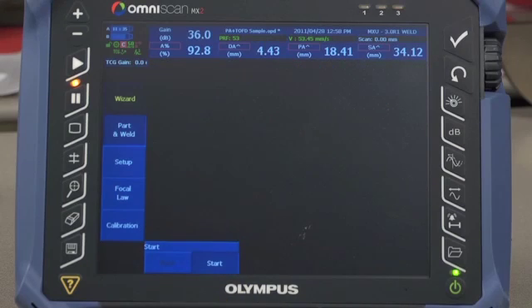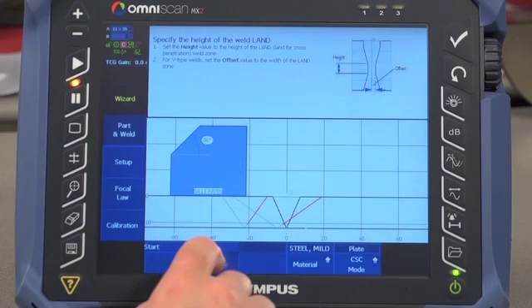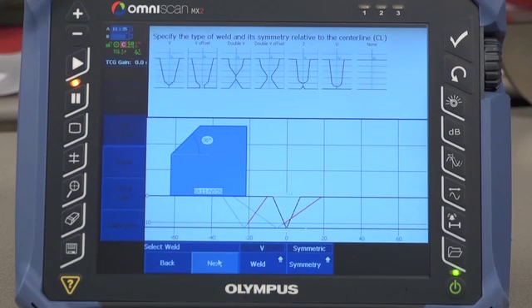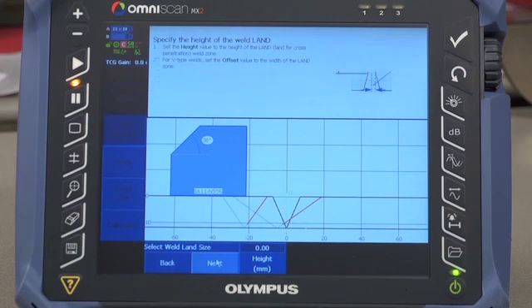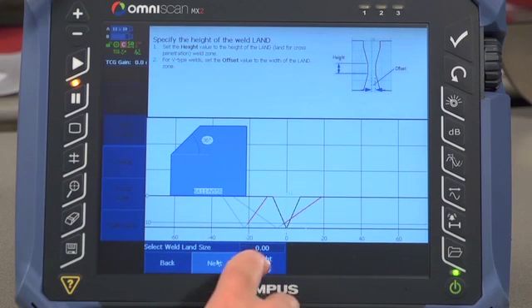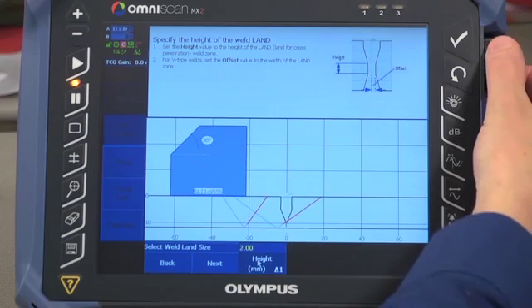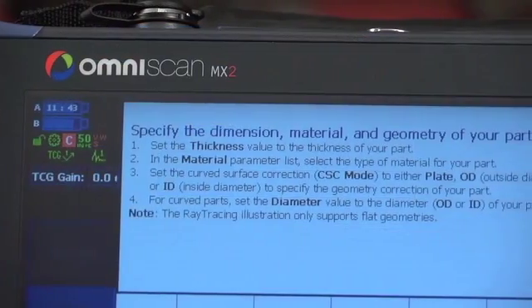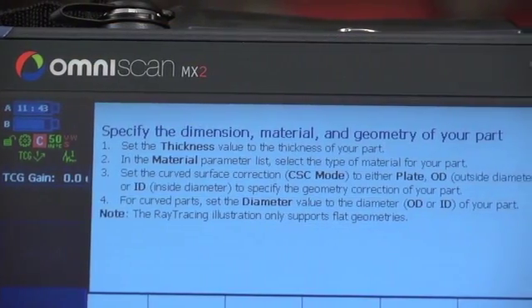Ultrasonic, TOFD, and phased array setups, as well as code-compliant calibrations, can be easily created using wizards. These wizards guide the user through all the required inputs and parameter adjustments, with explanations provided by an interactive help menu.